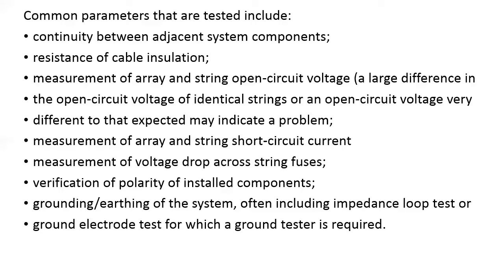And of course, the measurement of array and string short circuit current will be hazardous if it has not been checked properly. Then the measurement of voltage drop across string fuses, that is, whether there is any voltage drop across your string fuses, has to be checked. The verification of the polarity of the installed components.